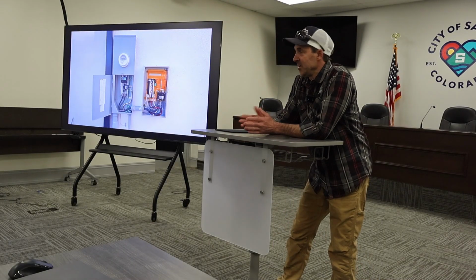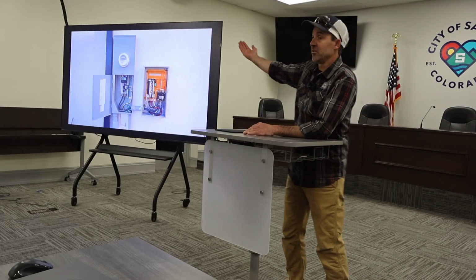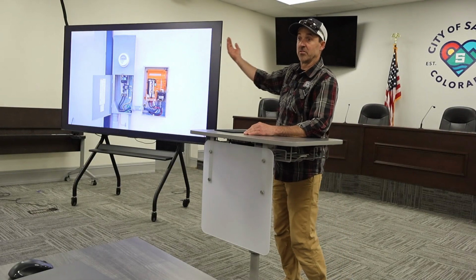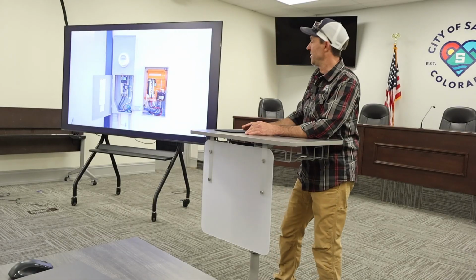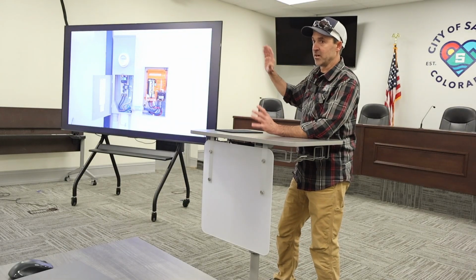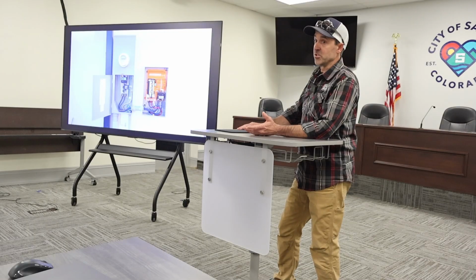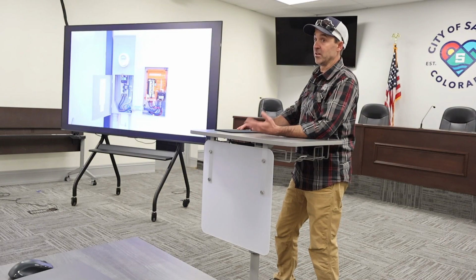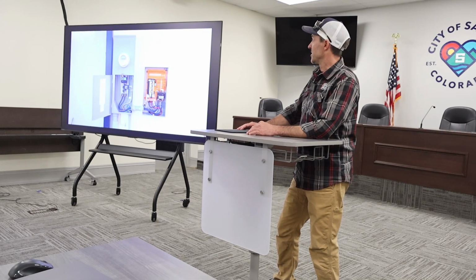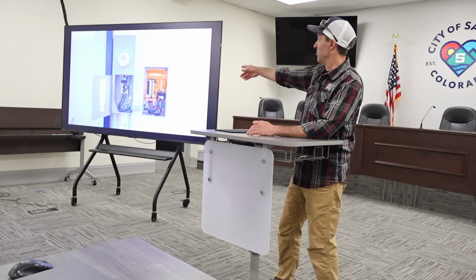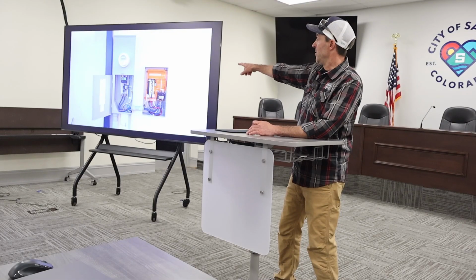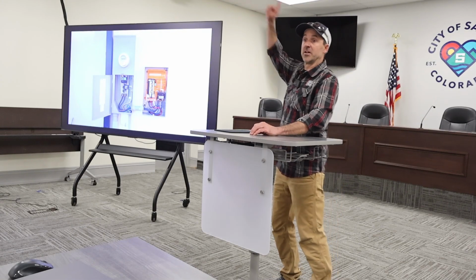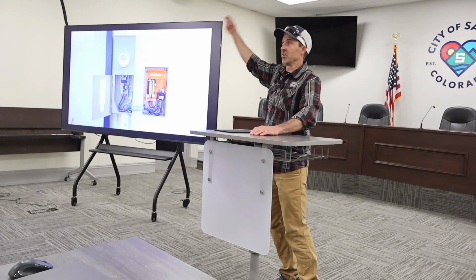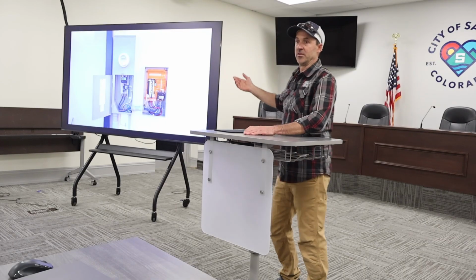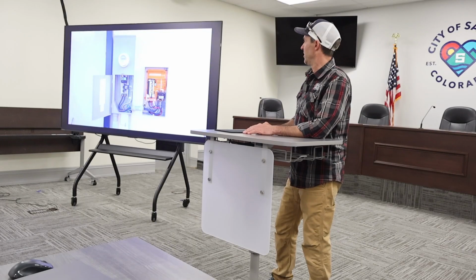We're trying to figure it out, because sometimes you'll have an all-in-one like this with the main panel right on the other side of the wall. So we're within 10 feet, but anytime we feel uncomfortable we just meter collar it so we know we're good. But those aren't cheap, a meter collar is $450 and you need a fuse disconnect too, so there's some cost. A lot of times now these homes have an all-in-one on the outside, but the electricians run those feeders to the other side of the garage instead of running wire across the whole house, so then you're way over that 10 foot, and that's how you have to handle it.